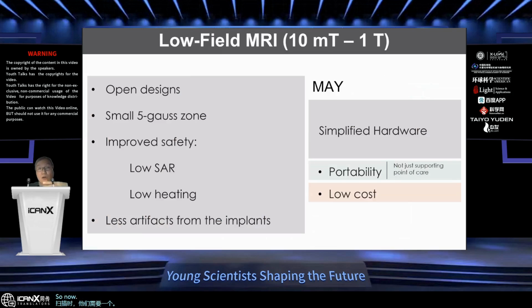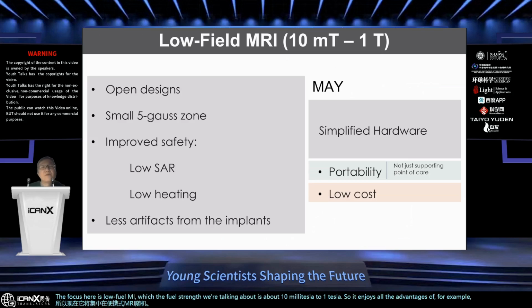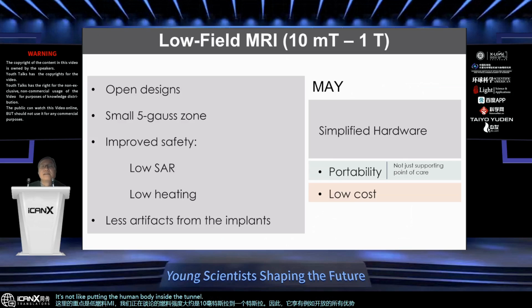So now if we focus on portable MRI, the focus here is low field MRI, where the field strength we're talking about is about 10 millitesla to 1 Tesla. It enjoys all the advantages: it's open, it's not like putting the human body inside a tunnel, and it's compact, with a small 5 Gauss zone. The 5 Gauss zone means that outside the zone it is very safe to have metal, for example a pacemaker or scissors, etc. A smaller 5 Gauss zone makes the machine compatible with a lot of locations, for example an ambulance.